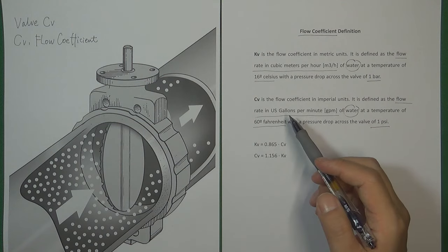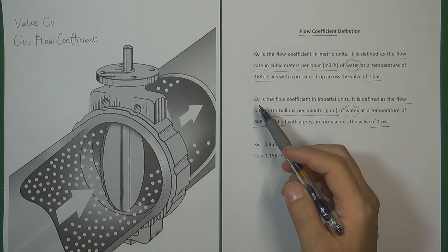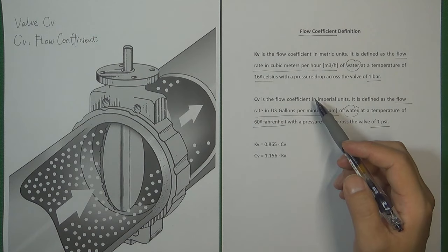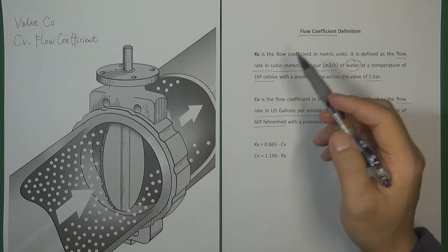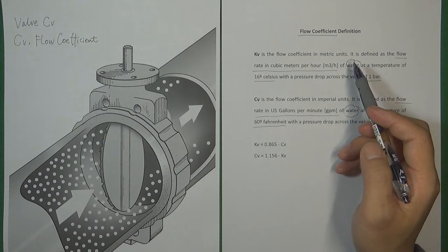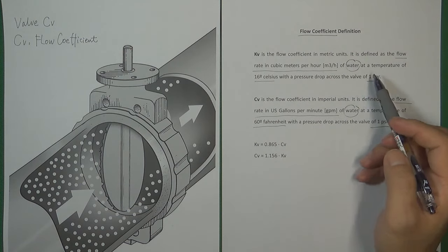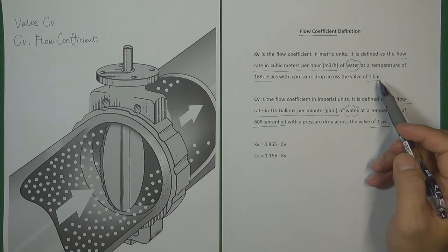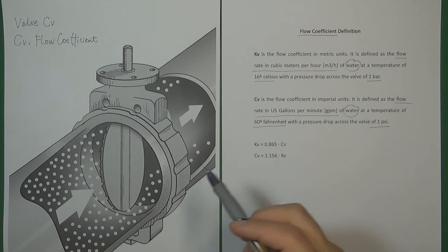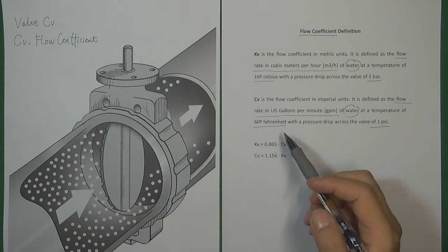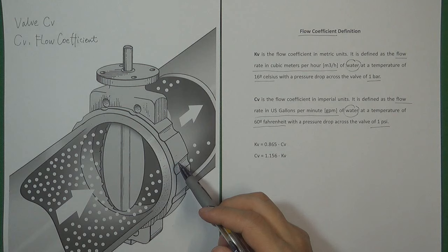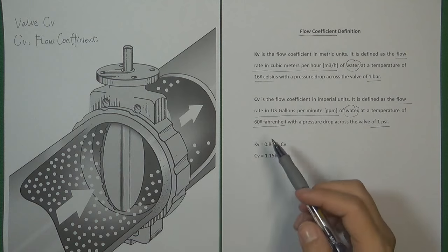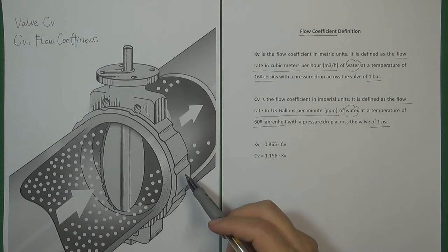That is very easy to understand what valve CV testing is. Because CV is based on imperial standard. In metric standard, there is also another flow coefficient called Kv. The basic testing and principle is the same, just using different units. We can use this kind of testing to get a correct valve CV. The question is why we need to do this kind of testing, and when we are going to use the CV in the flow control system.